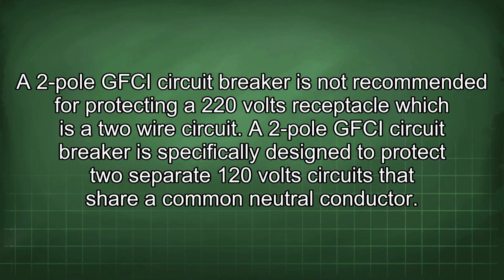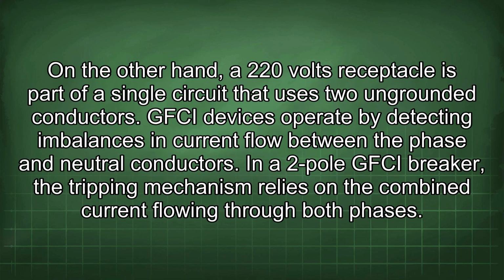A 2-pole GFCI circuit breaker is not recommended for protecting a 220 volts receptacle, which is a 2-wire circuit. A 2-pole GFCI circuit breaker is specifically designed to protect two separate 120 volt circuits that share a common neutral conductor. On the other hand, a 220 volts receptacle is part of a single circuit that uses two ungrounded conductors.